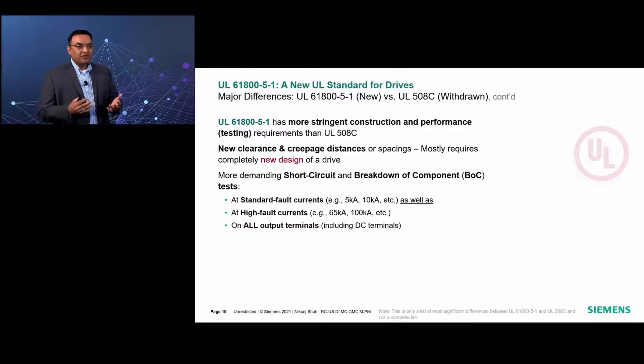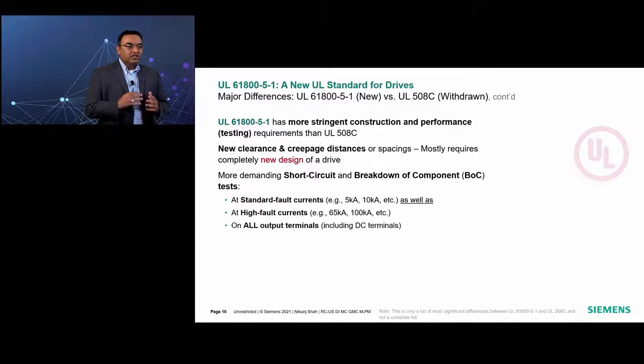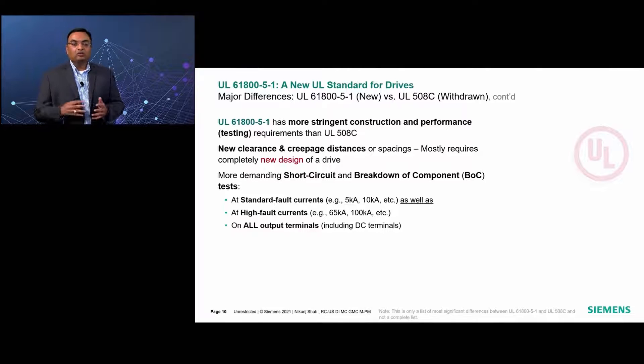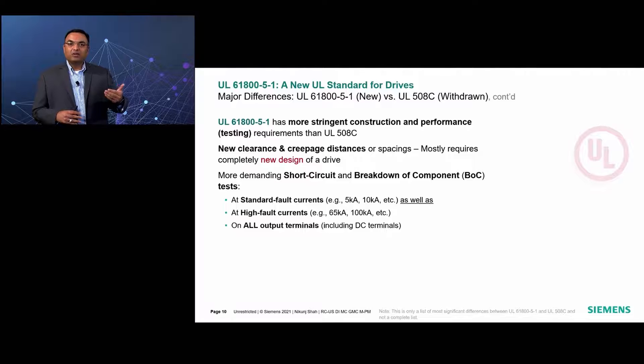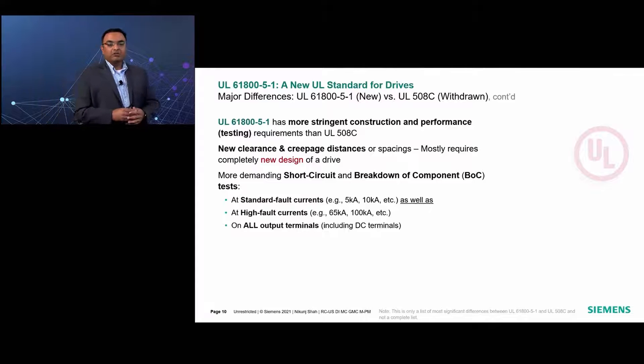This also includes the DC terminals in addition to the AC output terminals where motor connections are made. Most general purpose drives have these DC terminals, which are used for applications such as DC coupling or braking. However, according to the old UL508C standard, these DC terminals were not required to be short-circuit tested. Based on this new requirement in 61800-5-1, now they are, which means more destructive tests are performed on a greater number of test samples.